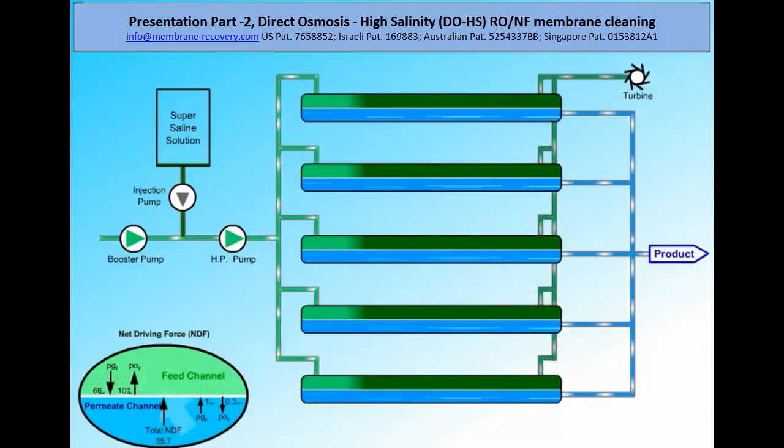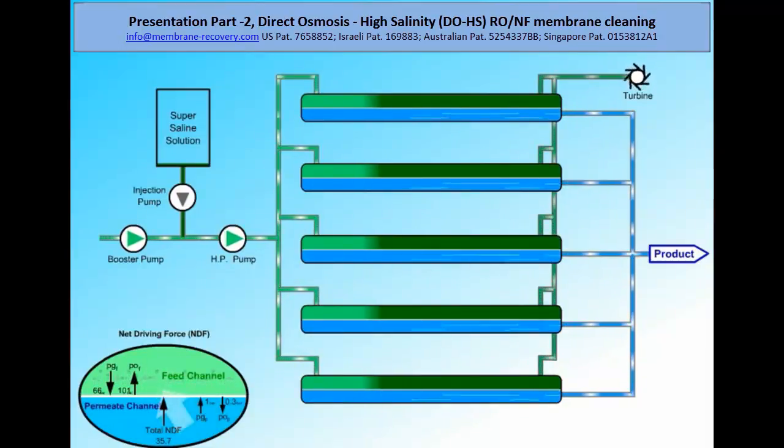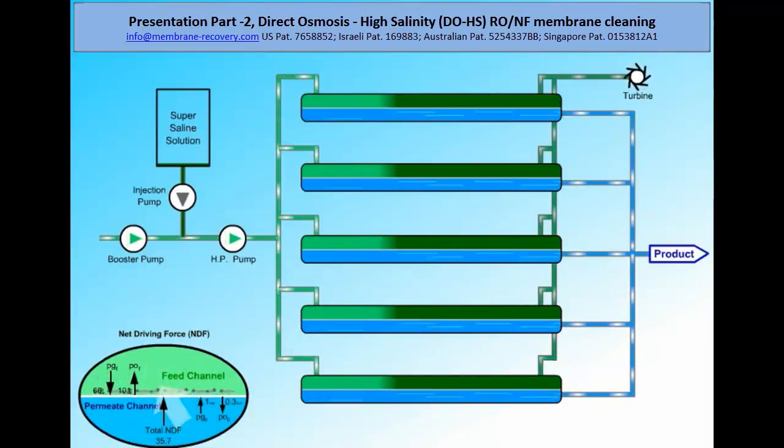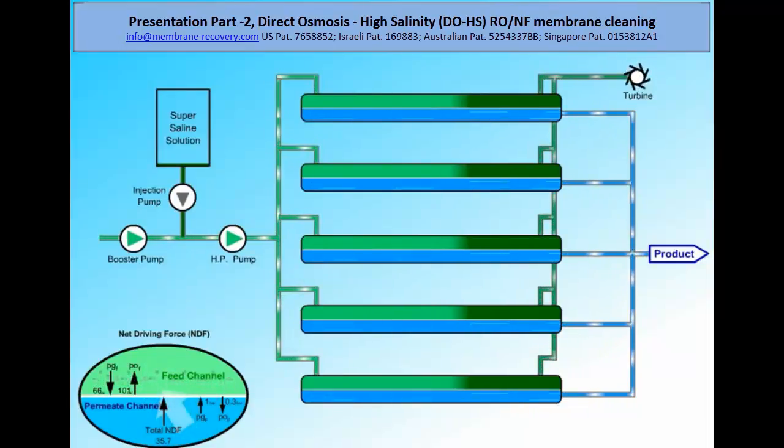And third, control the right reject flow movement with fouling out from pressure vessels. In the oval below, it's clear that the net driving force is redirected from a reverse osmosis to a direct osmosis process. The permeate moves from a permeate channel into a feed channel.